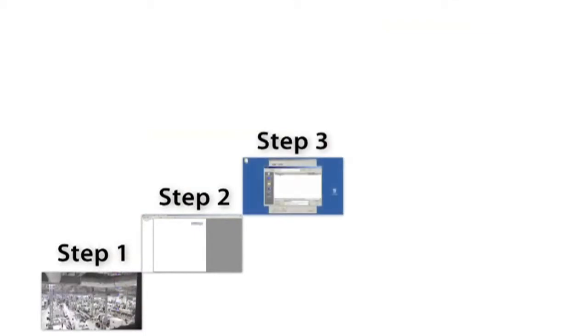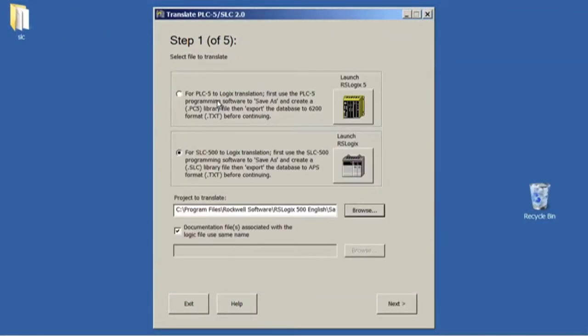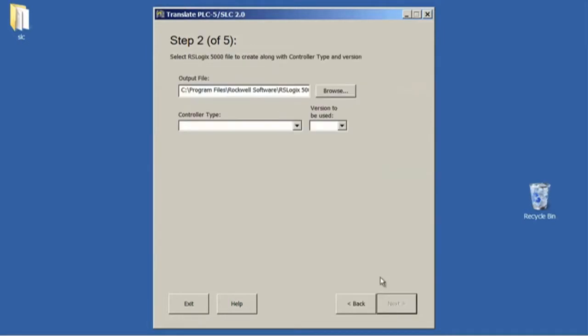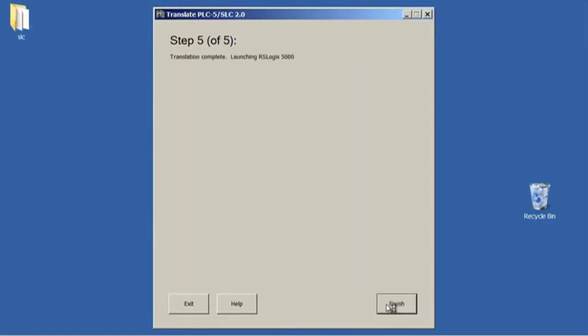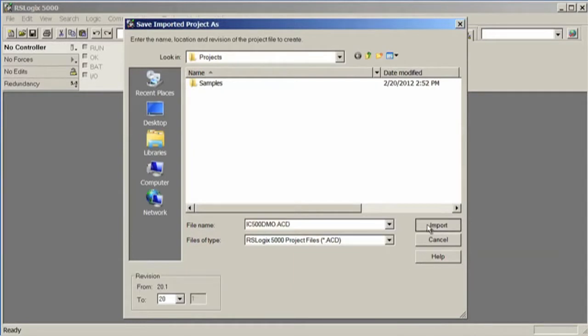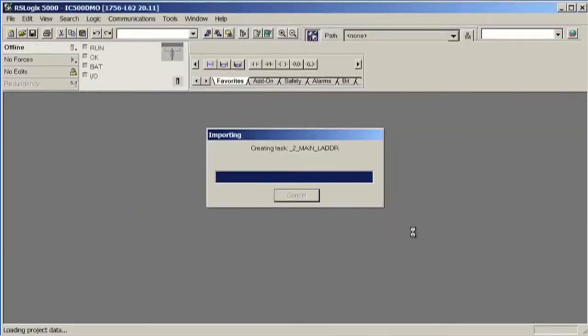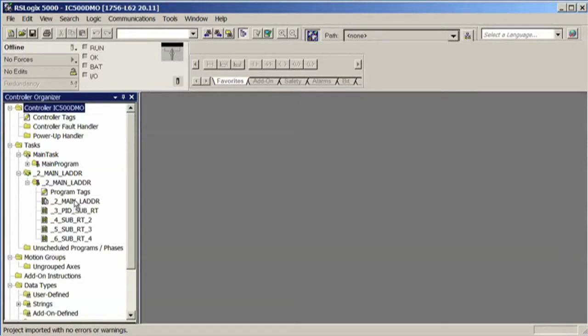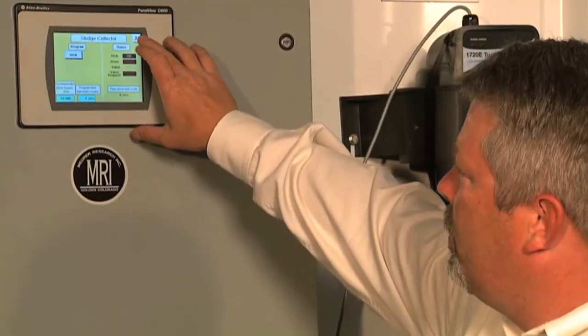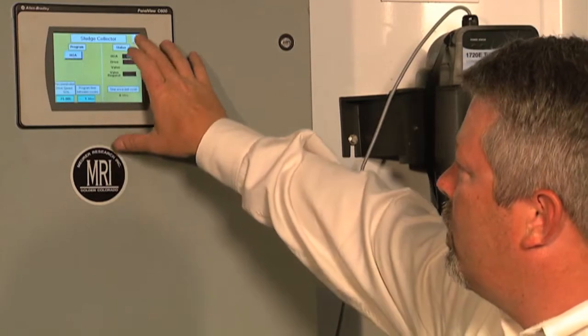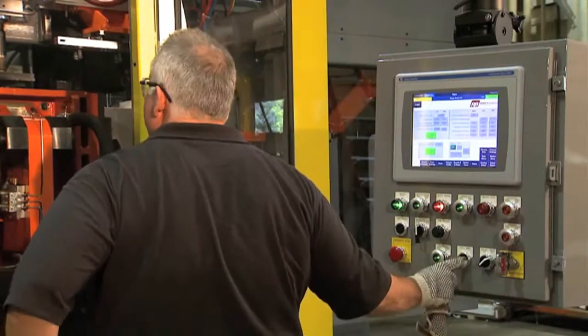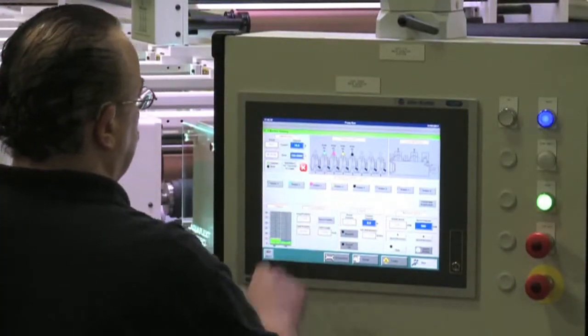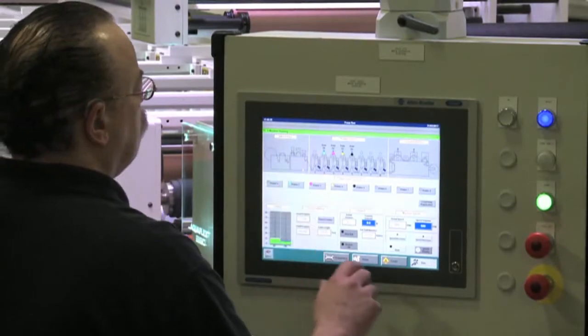Step 3. Save time and engineering resources by using the embedded conversion utilities for both PLC and HMI applications. RSLogix 5000 design and configuration software allows you to convert your existing RSLogix 500 program to RSLogix 5000 code. Graphic conversion utilities are available for PanelView Enhanced, PanelView Standard, and non-Rockwell Automation HMIs. Using these tools makes the conversion much more cost effective, as well as providing greater flexibility regarding the final product.